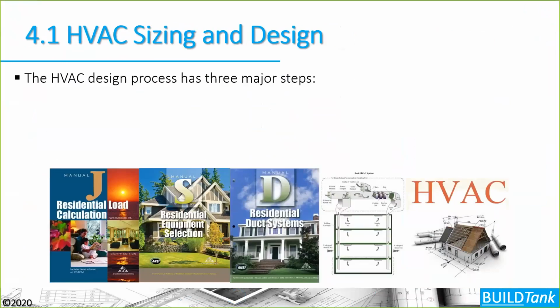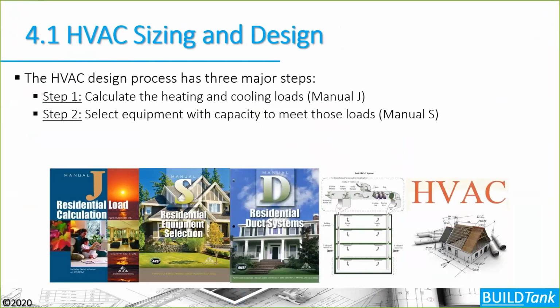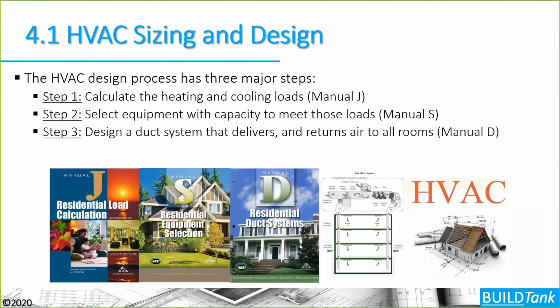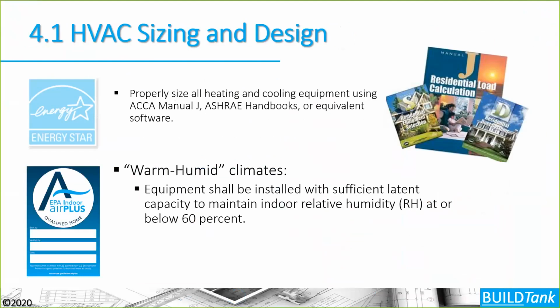So as we talked about last time, this program requires proper HVAC sizing that involves calculating the heating and cooling loads in our houses, selecting the right equipment that has the proper capacity to meet those loads, and then designing how we're going to distribute those loads around the house, either by pipe or duct, or however we're going to do that in our particular house here. So proper sizing happens through the ACCA manuals or the ASHRAE Handbook of Fundamentals. In warm climates, again, keeping that humidity down low.